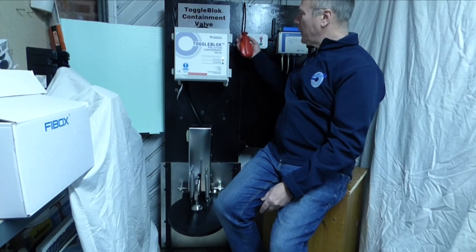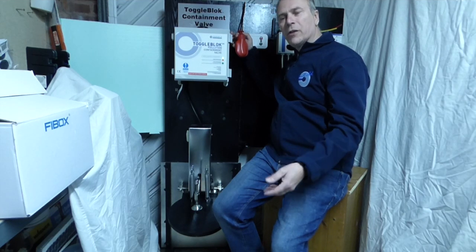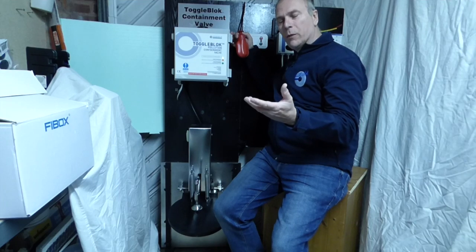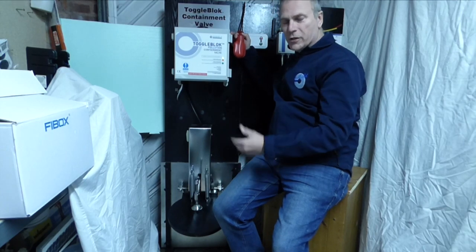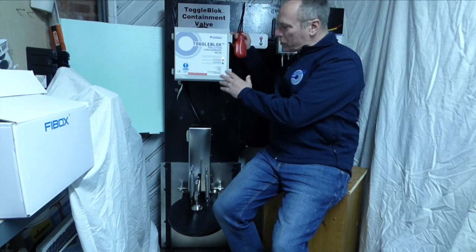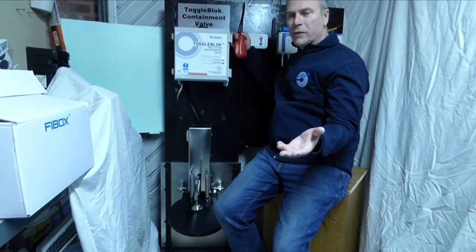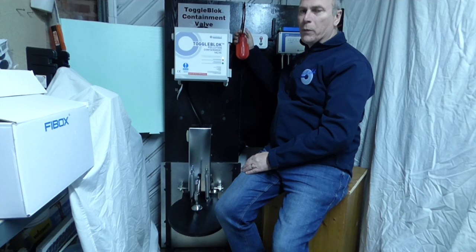What I've done here is place a float switch. You could have this in a sump — for example, a site with an effluent treatment process and a sump in the ground, where if it rose up and overflowed it could potentially reach the surface water network. The inquiry we had was from a site that already had a ToggleBlok system on their drainage network; there was a manhole in the effluent treatment plant process area, and what they wanted was for the valve to automatically close if the effluent treatment plant sump ever filled up, sending a signal about the fault while also preventing any contamination from reaching the surface water drain.